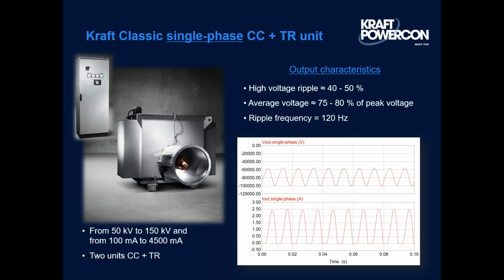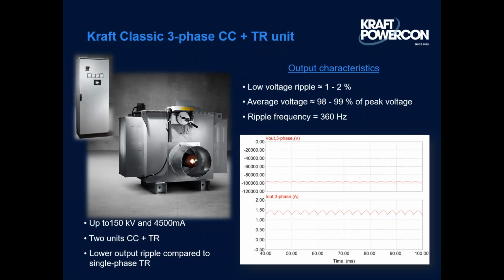If you go to the next slide, here's your high voltage ripple, 40 to 50%, average voltage. Now our Kraft Classic 3-phase TR set took the same reliability we had in our single phase and tried to get closer to a true DC. We achieved this very closely - you have a ripple of like 1 to 2%, so it's basically a flat line. It still has a separate control cabinet because it's 3-phase instead of 1-phase, and it's larger by weight and overall physical dimension. But it carries the single phase reliability - it's exactly the same, instead of 1 rectifier bridge, it's got 3 rectifier bridges, but it's the same bridge. So this has been a good product.